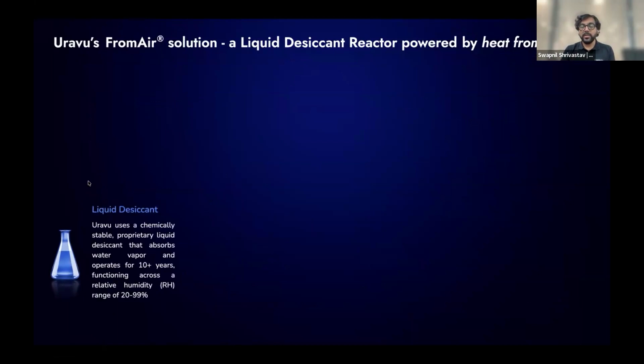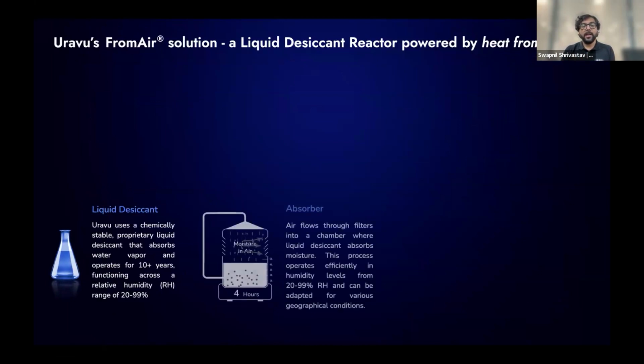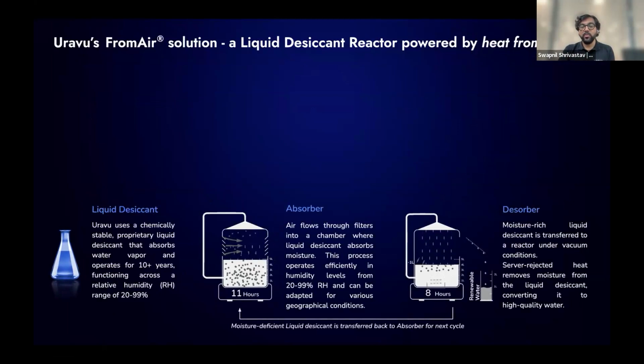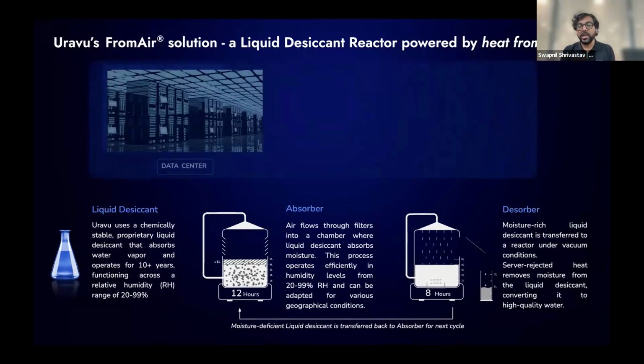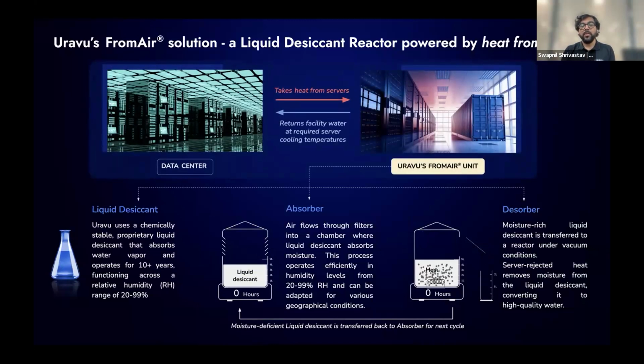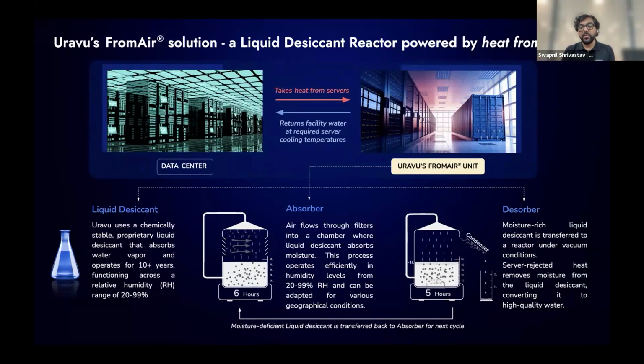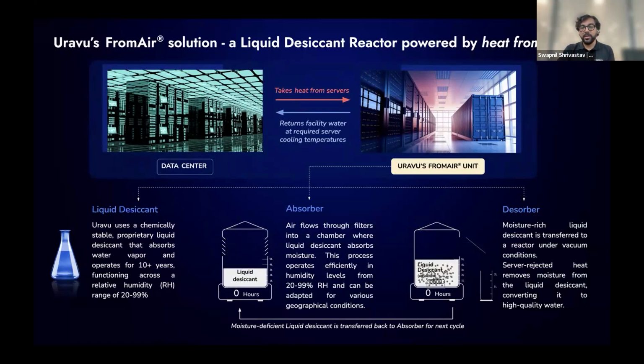So how the solution works in our case is we use a proprietary liquid salt which absorbs moisture from ambient conditions as low as 20% humidity. We then let it pass through a chamber where the air and liquid salt interact. It absorbs the moisture, and then finally we apply heat coming from your facility water loops and convert it to high quality water. Because of AI, heat loads are increasing and you're getting much higher temperature heat. You're not constrained by 5 to 15 kilowatt server racks anymore; now you have 150 plus kilowatt racks, going up in future designs to a megawatt, which is where the industry is moving. So while your heat intensity has increased, your heat temperature has also increased, which makes it viable for such use cases to emerge.